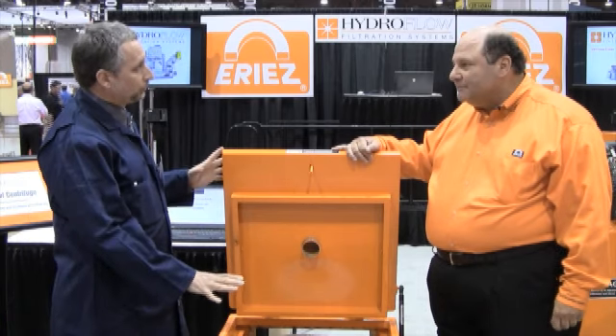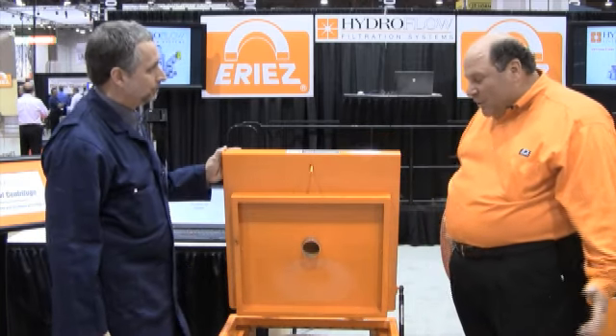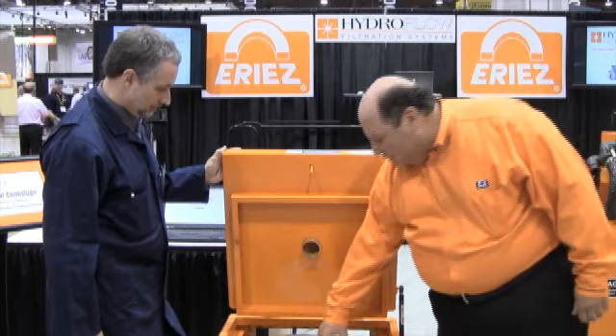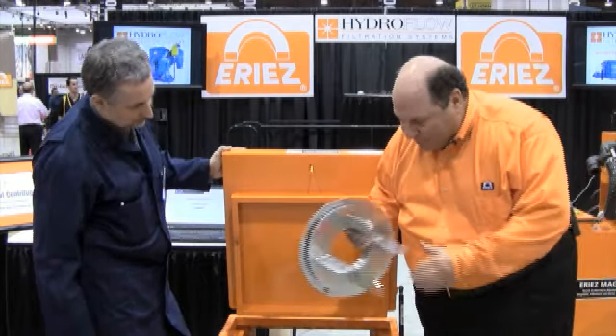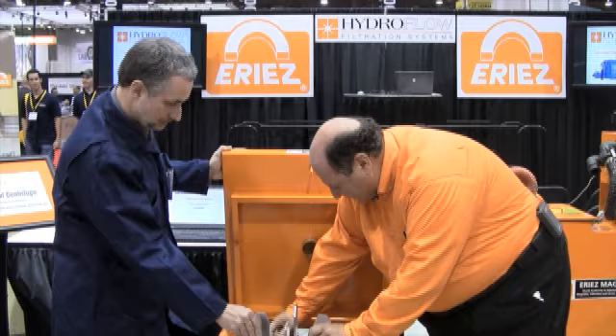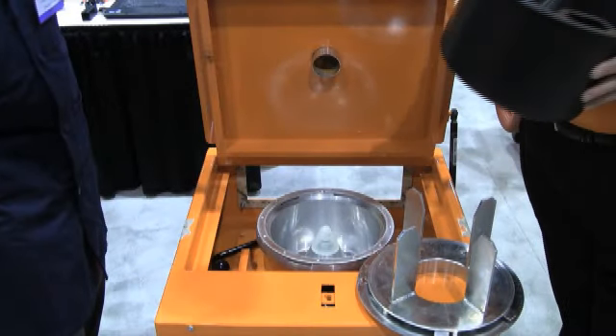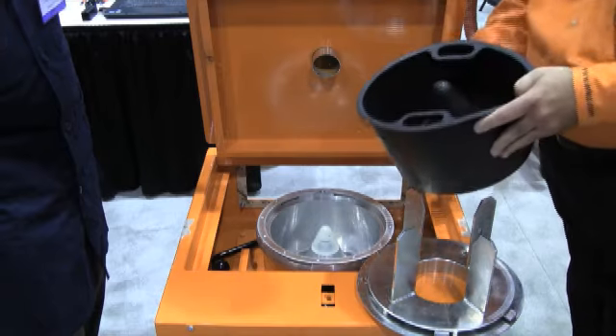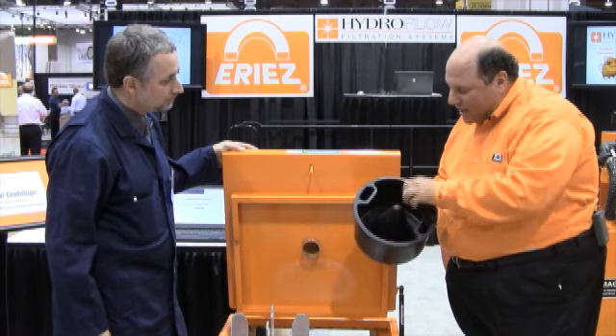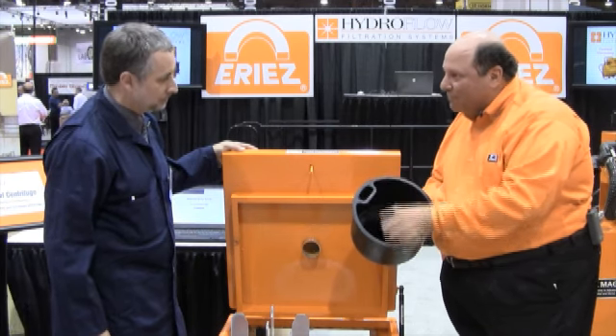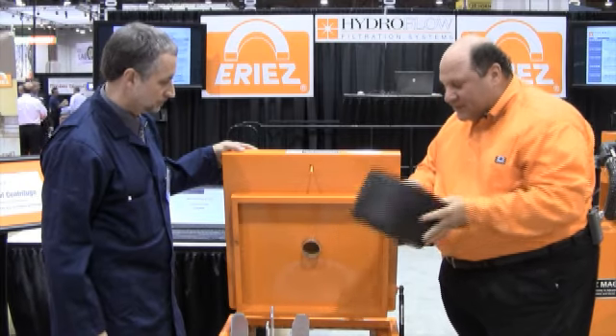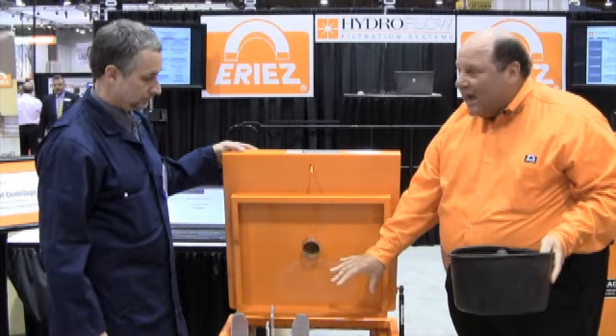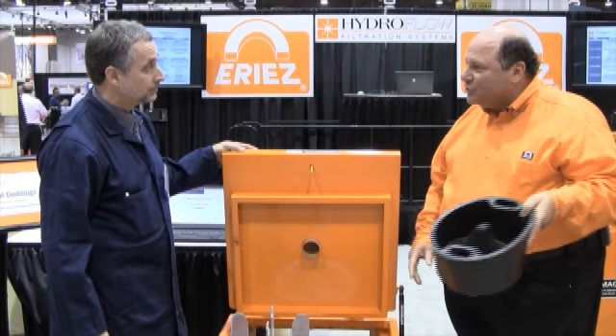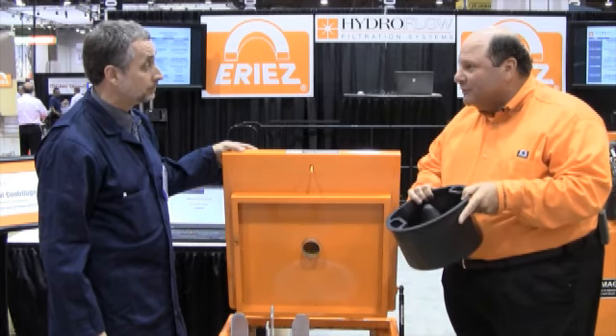In terms of maintenance, what's required to keep this unit running? Very little. One nice thing with this particular unit is it's got what we call a vane assembly. This is rotating at 3,400 RPM, and we've got a removable bowl liner. As it spins, it pushes the solids to the wall of the bowl liner. When you need to clean it, you simply pull it out, put a new liner in, and the next day you've got a dry, solid cake of whatever your solids were.